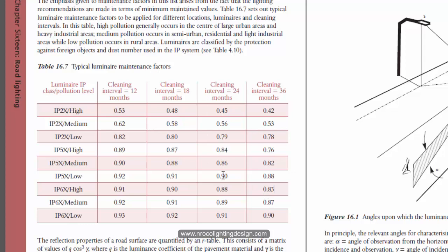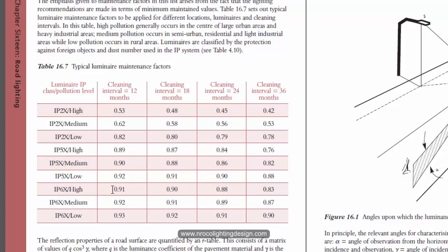And if it's for 18 months you can have 0.9, and it's really high for a maintenance factor I can say. So if your fitting is high rated like IP65 you can place or you can use 0.9 or even 0.91 as your maintenance factor.